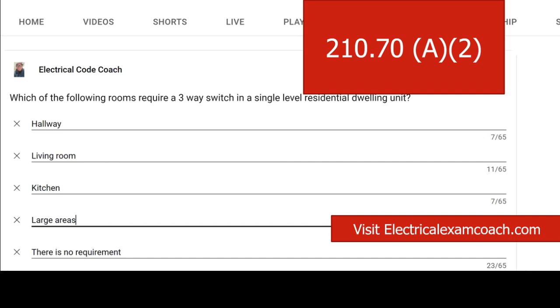Now, there's some other things that you have to watch out for with that code. If that set of stairs stops at a landing and there's a door off that landing, you would also have to have a three-way switch there. So it'd be a minimum of one at the bottom, one at that landing, and one at the top.